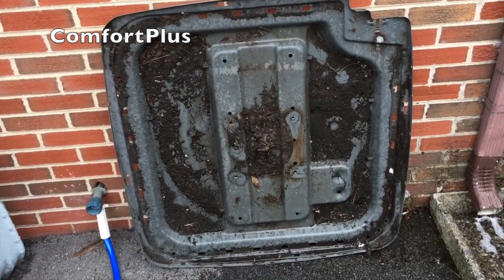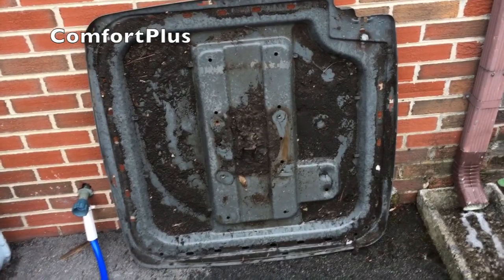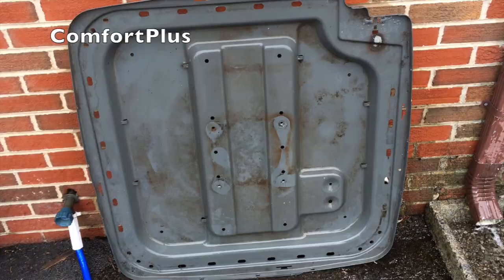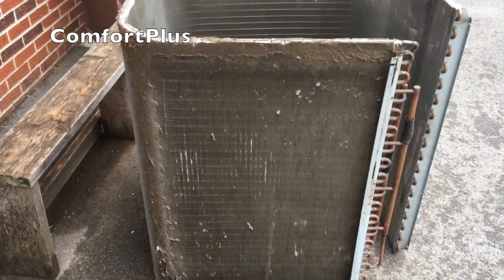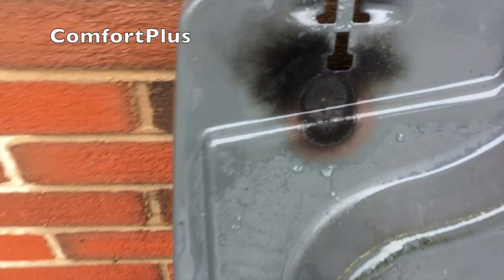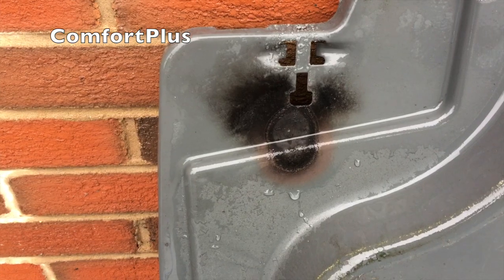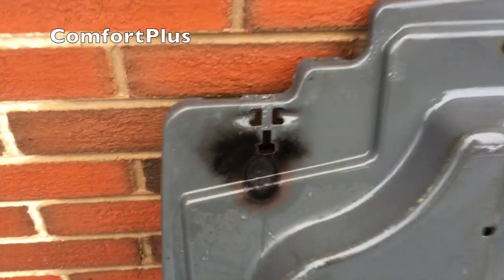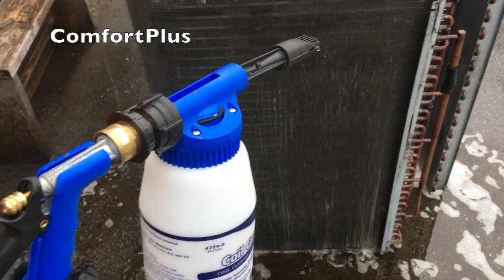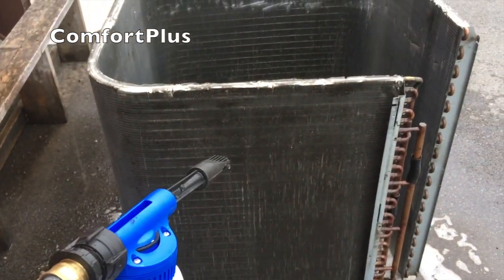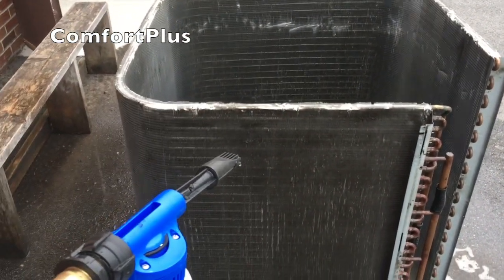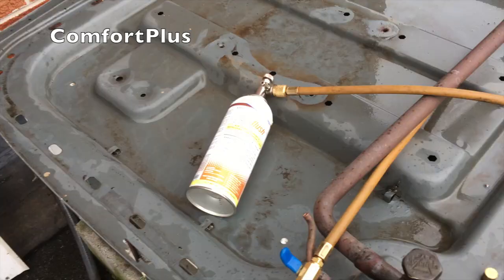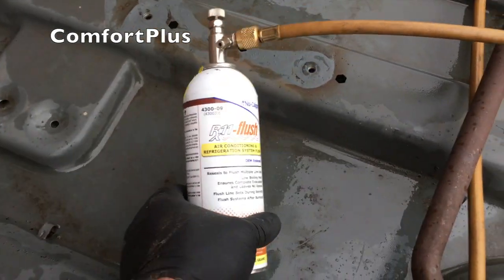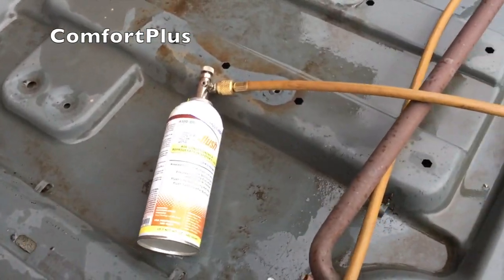Took 3 screws out of the service valve and just brought that pan over to the hose to wash it out. Probably do the same thing to this coil. And apparently they did replace the dryer when they replaced the compressor, because otherwise that pan wouldn't be burnt like that, I would think. Trying out my coil gun. My good friend John Israel sent this to me last winter, and this is the first chance I've got to use it. Okay, going to flush out the different segments, including the condenser coil, using some flush.